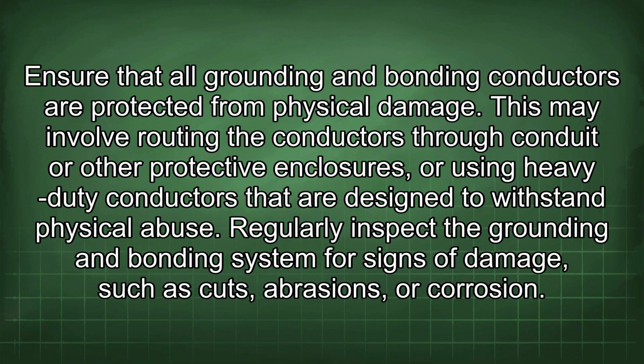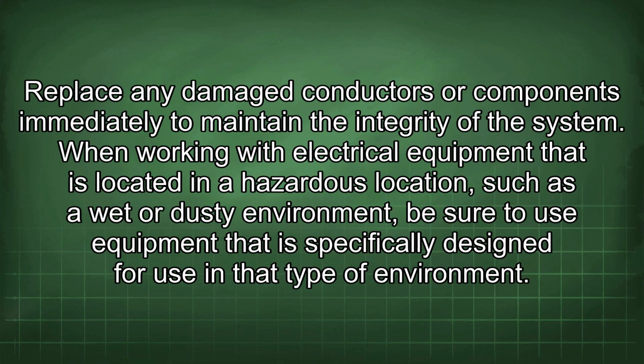Ensure that all grounding and bonding conductors are protected from physical damage. This may involve routing the conductors through conduit or other protective enclosures, or using heavy-duty conductors that are designed to withstand physical abuse. Regularly inspect the grounding and bonding system for signs of damage, such as cuts, abrasions, or corrosion. Replace any damaged conductors or components immediately to maintain the integrity of the system.